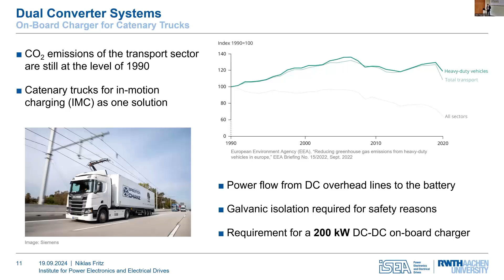So we faced a particular problem at the beginning of this project: we were faced with two different voltage levels. On the test track installations, there were 600 volt installations, and for the highways, 1,200 volts were planned. To address this, we came up with a solution of building a 200 kilowatt converter by interconnecting two 100 kilowatt units. To attach to the 600 volts, you can put them in parallel on the primary side, and to attach to the 1,200 volts, you connect them in series on the primary side.